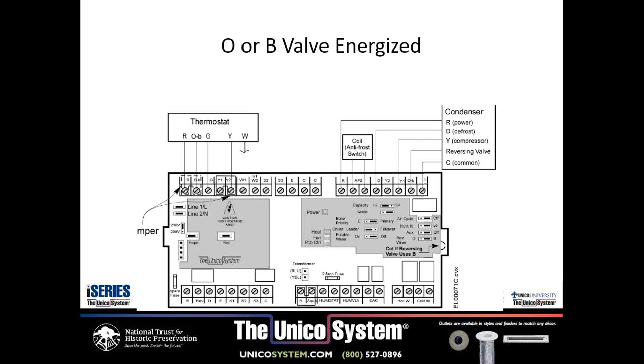So this is the wiring diagram, how we would energize the heat pump. Heat pumps can be energized in one of 2 methods. The vast majority of heat pump manufacturers energize the heat pump on O, which means it comes on when it's calling for cooling. One brand in particular, Rheem and Ruud, energize on the B valve. So we allow you either way to do this. It's just merely where you set the switch, and if you do have a B valve, you do have a wire that you have to cut.